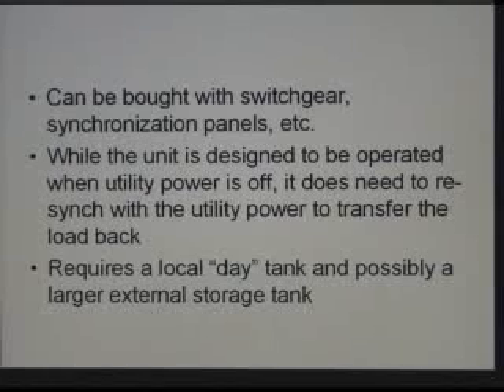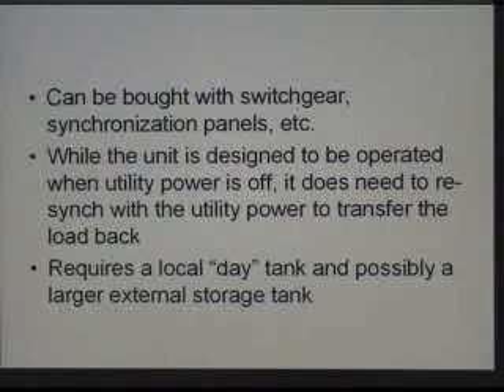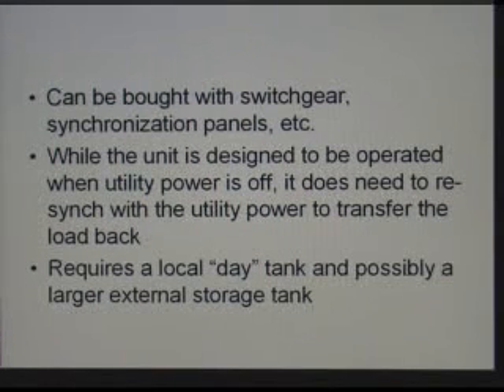At some point in time, utility power gets brought back on. And so now you've got the whole rest of the plant operating on utility except your emergency bus. And now you have to bring the two back together again and get them in phase so that you can do a semi-seamless transfer of power, and then you can take your generator offline. So that's what the synchronization panels are for, is to bring the phases together so that you can bring the electrical power systems together.